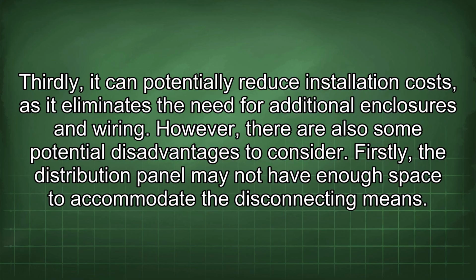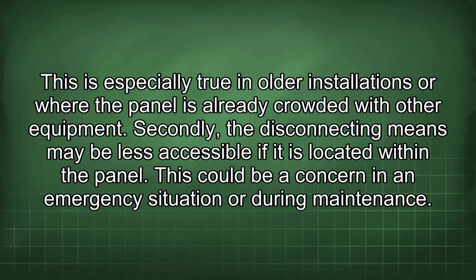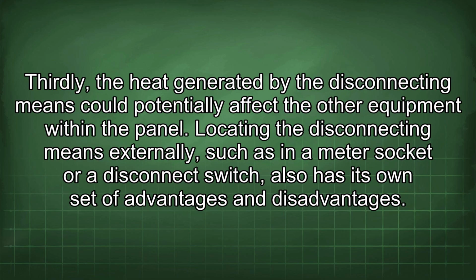Firstly, the distribution panel may not have enough space to accommodate the disconnecting means. This is especially true in older installations or where the panel is already crowded with other equipment. Secondly, the disconnecting means may be less accessible if it is located within the panel. This could be a concern in an emergency situation or during maintenance. Thirdly, the heat generated by the disconnecting means could potentially affect the other equipment within the panel.